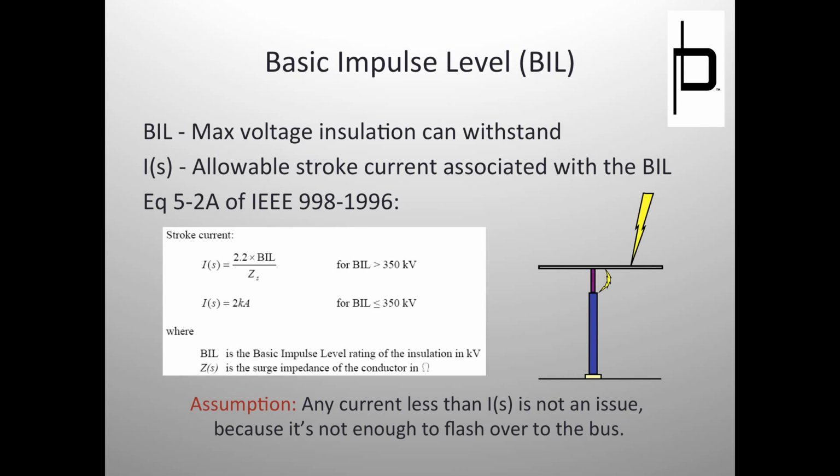Or if we do a lot of work near oceans, right? The salt water from the oceans, or we do a lot of work near construction sites, the dust and things like that. All these things that can contaminate the insulator may cause that insulator to flash over much earlier than 900 kV BIL. But again, nothing in lightning protection, nothing that we do is 100% short of the Faraday cage. But for practical purposes, we're going to assume that the 900 kV BIL does what it says it'll do.